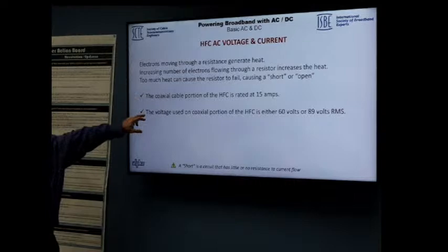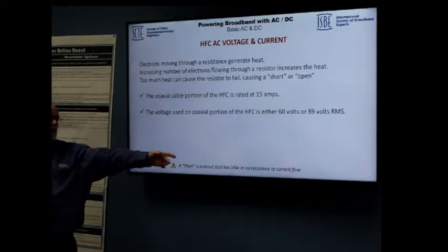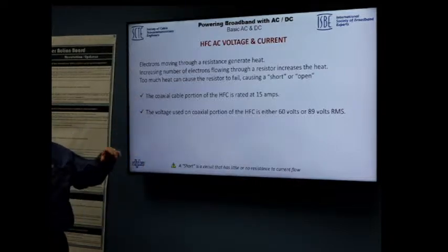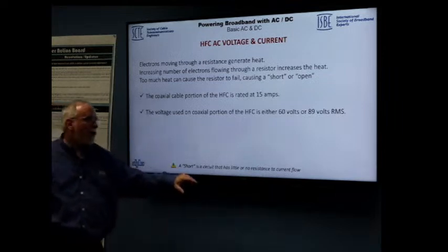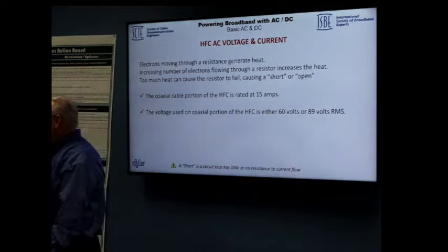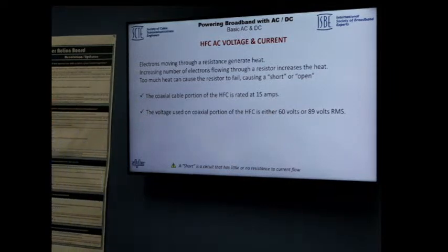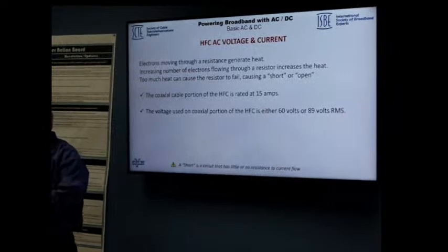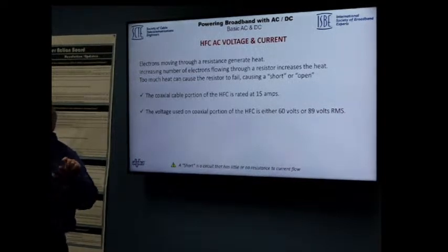The voltage on the cable plant is either 60, 72, or 89. 72 is pretty much not available anymore. The 60 or 63 volts, that's used a lot inside buildings. So the NESC is what we play with when we're outside plant. The NEC is what we play with when we're inside a house.